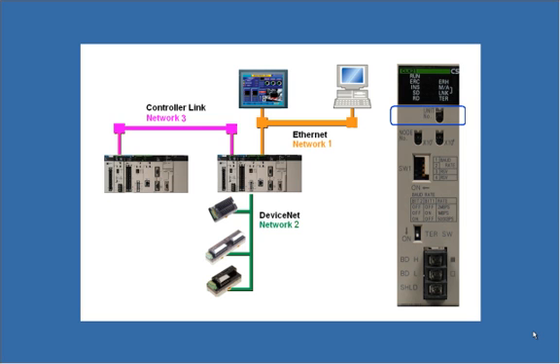The software tool that we will use to create and download the routing tables to the PLC is called CX Integrator, and this is part of the OMRON CX-One automation suite. The first step is to configure the PLC type and connection method used to transfer the routing table to the PLC. This is configured by clicking on the Communication Settings icon.